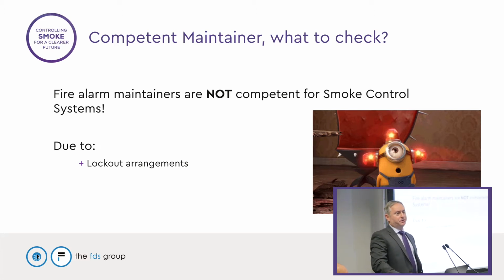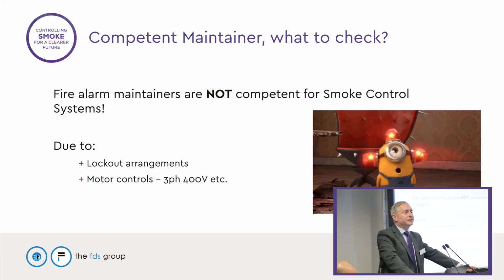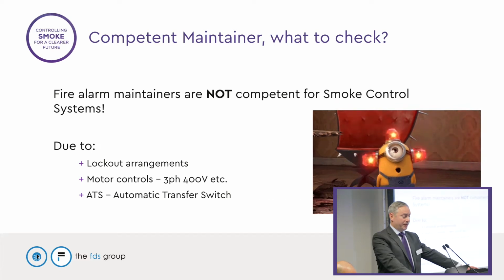They're also not familiar with motor controls. So if we have a mechanical system, we have some very large fans on the roof or in the car park or wherever we've located them. And fire alarm companies aren't specialists in motor controls. And they're often 3-phase, 400 volts, so a bit more dangerous and hazardous. And they don't really know how to deal with those and look at motor and fan maintenance. And then we also have something called the automatic transfer switch, which provides the changeover between our dual power supply. And this, again, is something that fire alarm systems don't generally have. They rely on a large battery in the bottom of the panel, which for their purposes is completely adequate, but for smoke control, it doesn't provide the duration we need.